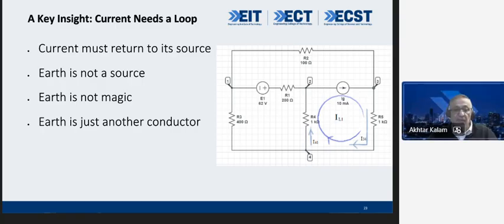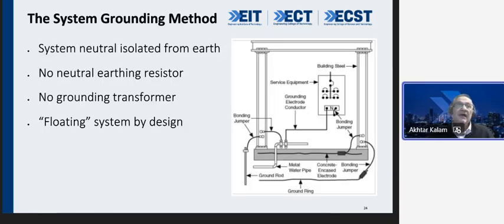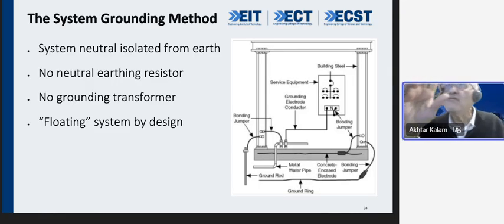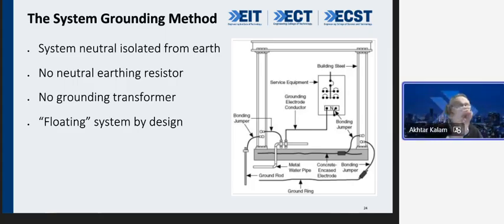So my friends, what I'm seeing now is the grounding method of the system, not of individual components of the system. The system neutral has to be isolated from Earth. There is no neutral earthing resistor. There is no grounding transformer. It's a floating system by design. And that's what I'm talking about. The system was intentionally ungrounded, something many engineers forget after commissioning. Many of them forget it.